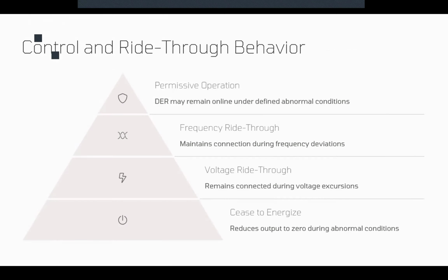Now, we said one of the most important requirements that addresses some stability challenges in our modern grid is the ride-through behavior and ride-through requirement. So let's talk about the permissive operation and what we mean first before we go to the ride-through. Now, the IEEE 1547 basically says that we have to have a permissive operation, meaning a DER is allowed and often expected to remain connected under a certain abnormal condition.